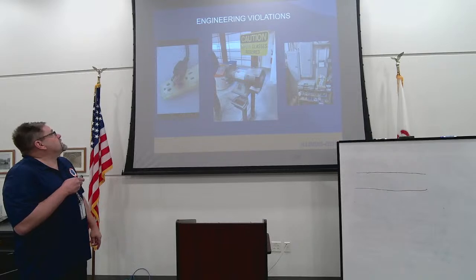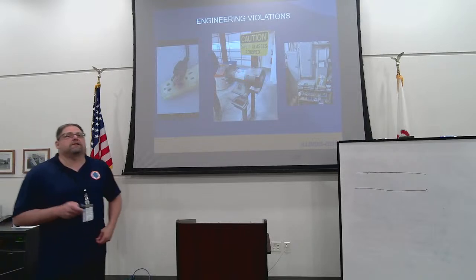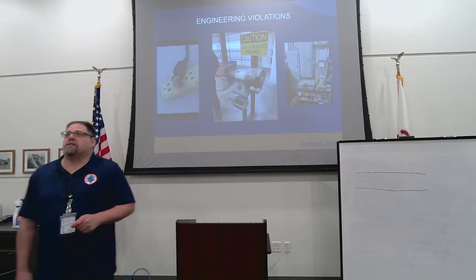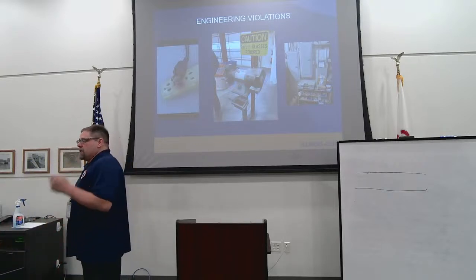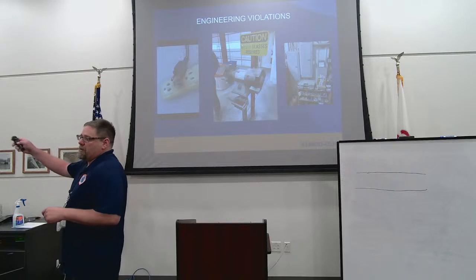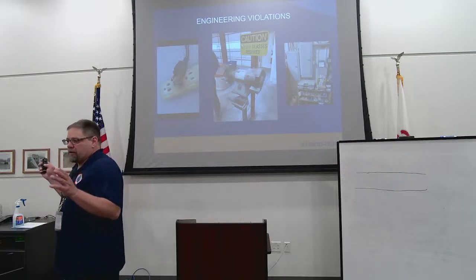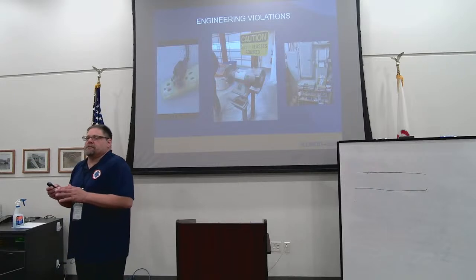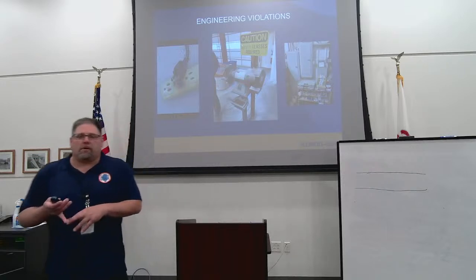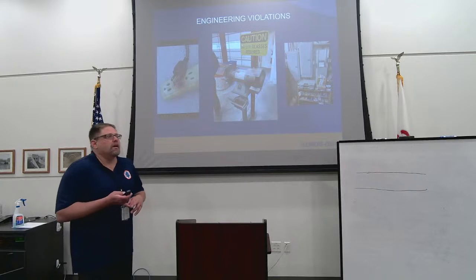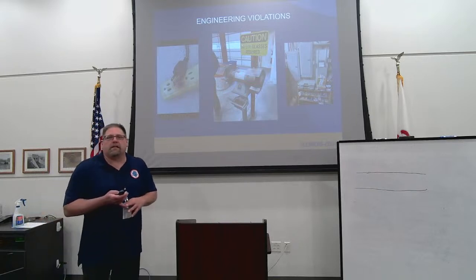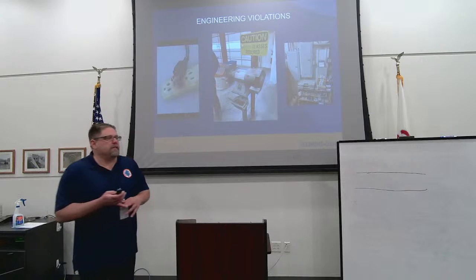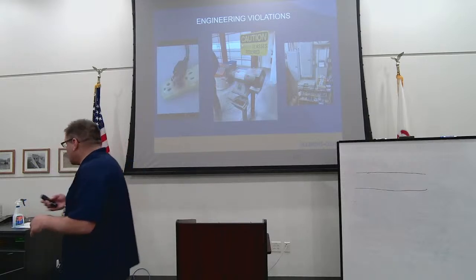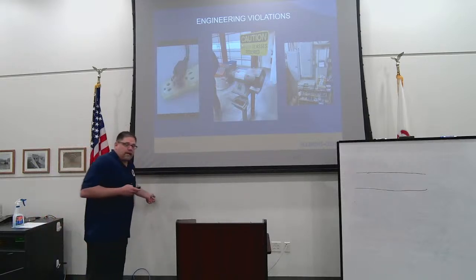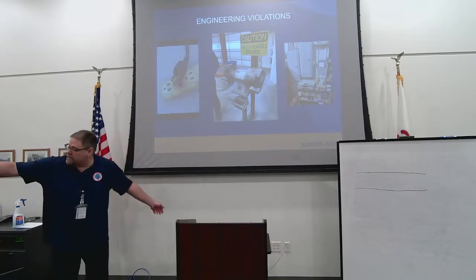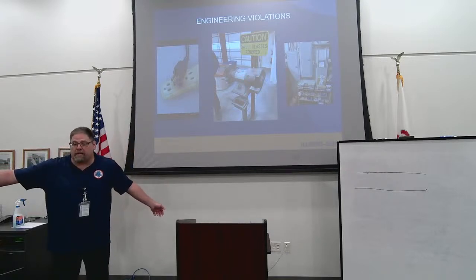Flexible extension cords - we cite this stuff all the time. They're not designed for continuous use. You don't staple them to the wall to run a pump in the aeration basin or whatever and call it good. The thing we see most often is they're using 16 gauge wire, the small little extension cord, and it will overheat. I'm not going to name the city, but it also happened in the last 2 months where I walked up to a cord they had stapled all the way around the building to the restroom, feeding a radiant heater.